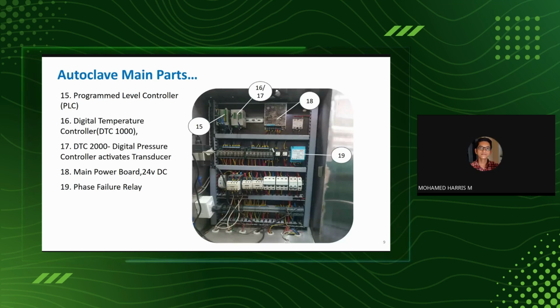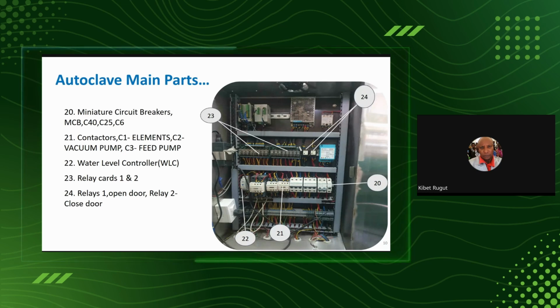Then there is the main power supply board. You realize that during troubleshooting, if you find that components are not working well, it is good to know if the power supply is stable. And because these equipments are sensitive to power, we have a phase failure relay that is inbuilt, and it is good to know that it plays a role in protecting the major parts of the autoclave. We also have breakers, which are controlling or preventing any overload in any part of the autoclave. There are those which just watch the control panel, those which watch the heaters, and also those which watch the vacuum pump and the feed pump, which is pumping water to the boiler. And so it's good to know that they are well arranged and labeled in the electronic panel.